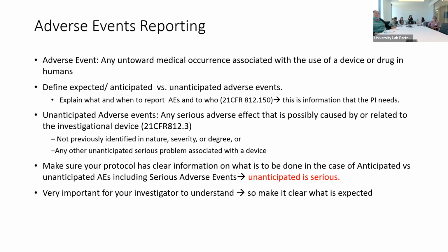And you can find those in 21 CFR 812. This information is out there. Do not expect the PI to be aware of it. Make sure that it is in your protocol, right? So that you have a clear set of rules and you say, hey, if these things happen, I as sponsor want to be notified within 2 days.